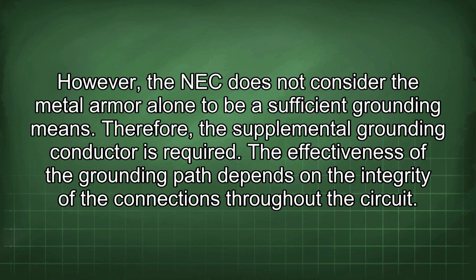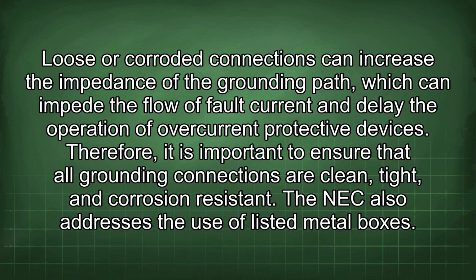The effectiveness of the grounding path depends on the integrity of the connections throughout the circuit. Loose or corroded connections can increase the impedance of the grounding path, which can impede the flow of fault current and delay the operation of overcurrent protective devices. Therefore, it is important to ensure that all grounding connections are clean, tight, and corrosion resistant.